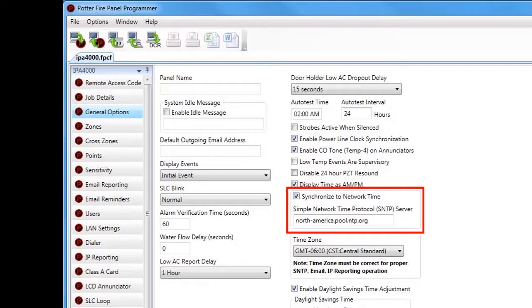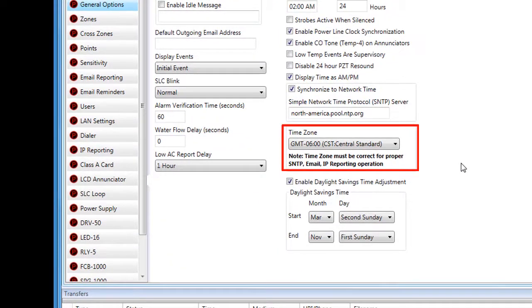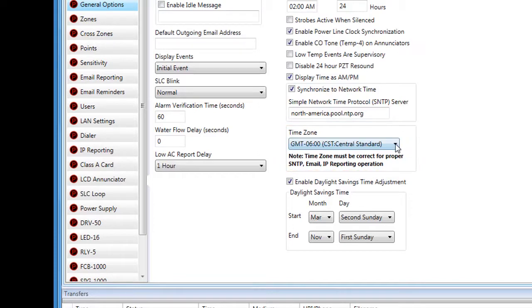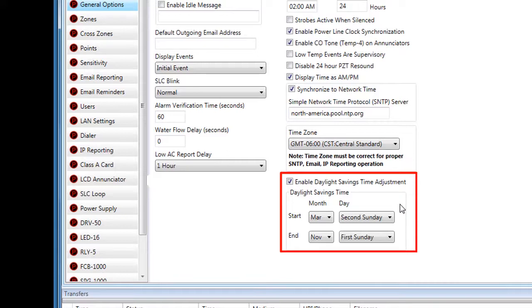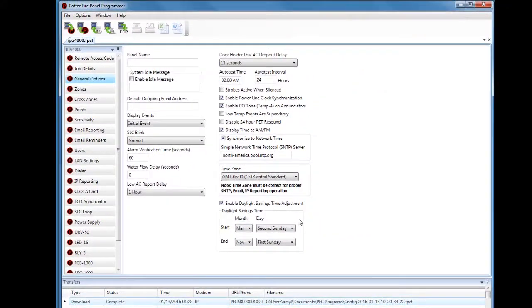Next is Synchronize to Network Time, checked by default. When checked, the panel will automatically obtain the time from the network it is connected to. If not connected to a network, you will need to set the time through the control panel keypad. You can also define the SNTP server from which the panel obtains the time, or use the default shown. You can then select your time zone — the default is Central Standard — with Eastern, Mountain, and Pacific also commonly selected. Enable Daylight Savings Time is checked by default, meaning the panel automatically adjusts for daylight saving time, with the adjustment dates in March and November configurable in the software if needed.